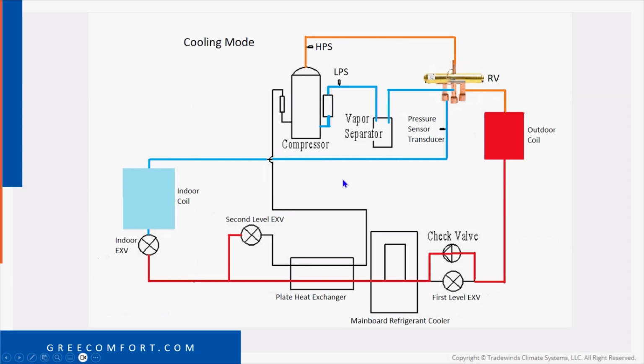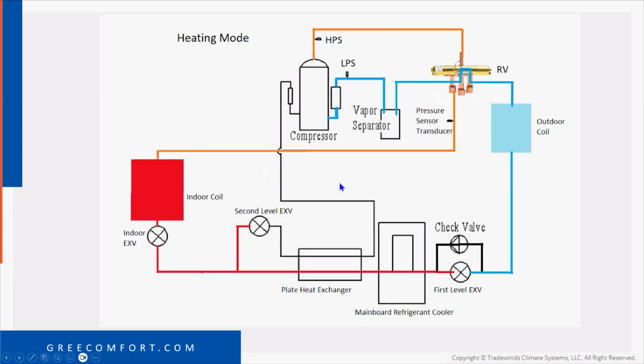So when we go into heating mode, again, we'll follow our flow from discharge gas through our reversing valve. We're discharging in the top of our reversing valve, coming out the left pipe here, discharging into our indoor coil, because we're in heating mode, releasing heat inside. And then we're not metering refrigerant here, so this EEV is going to be wide open, liquid flow back. Now again, there could be times where we'd actually subcool this refrigerant some, and this would also be used for low ambient heating.